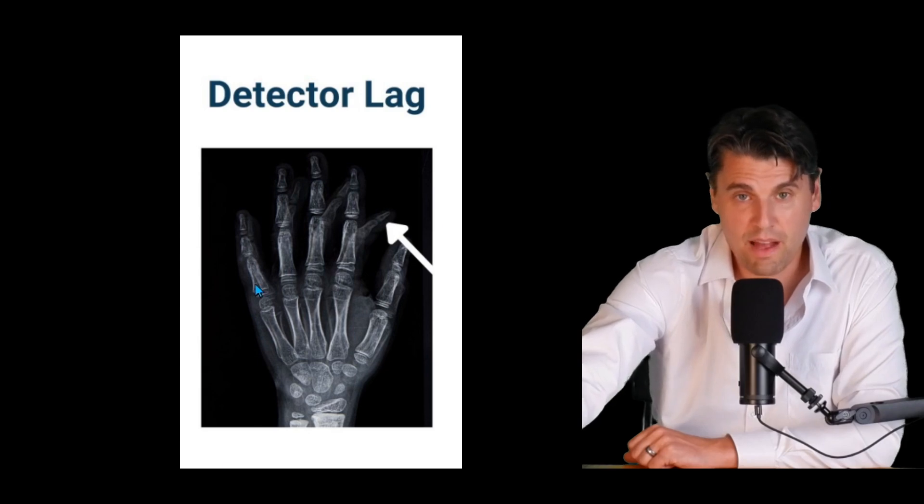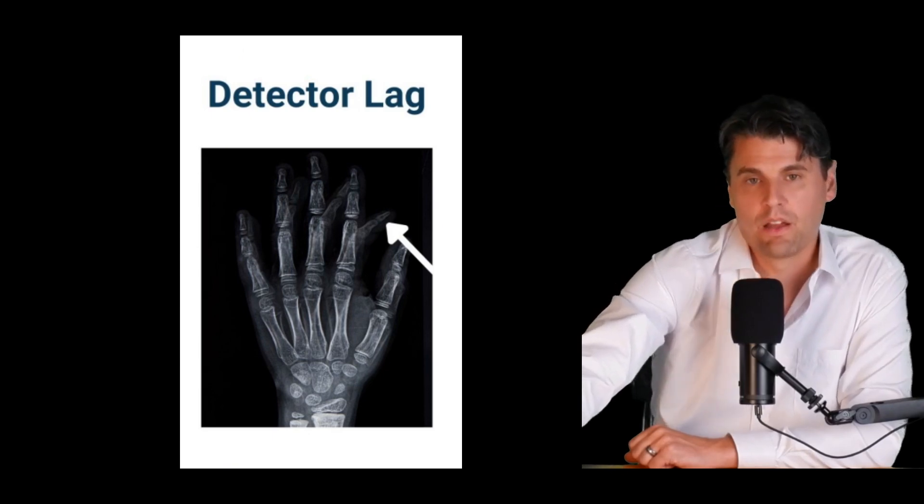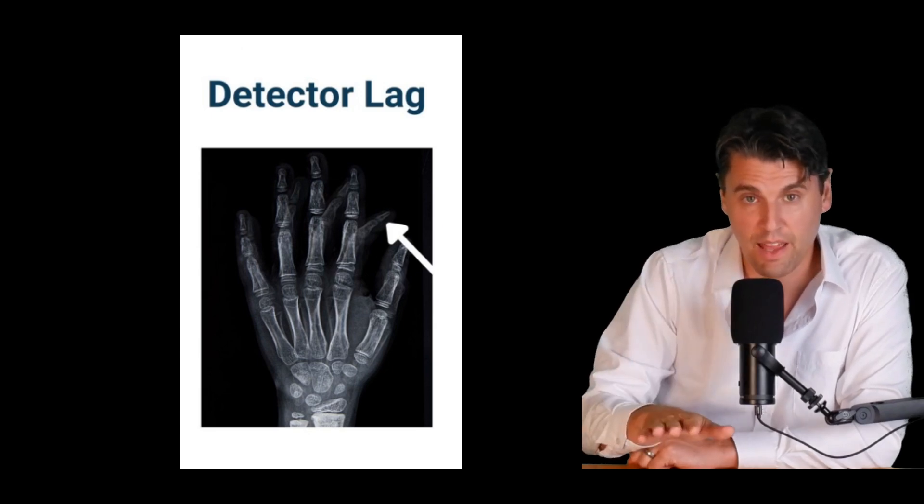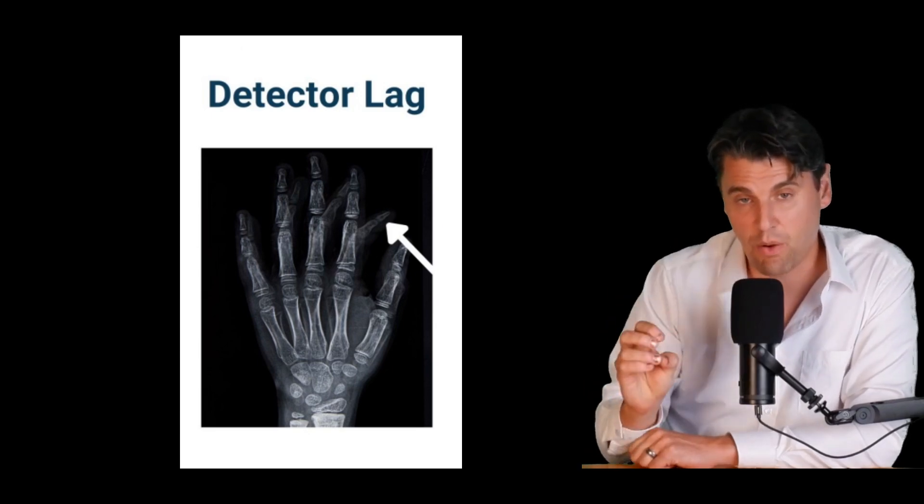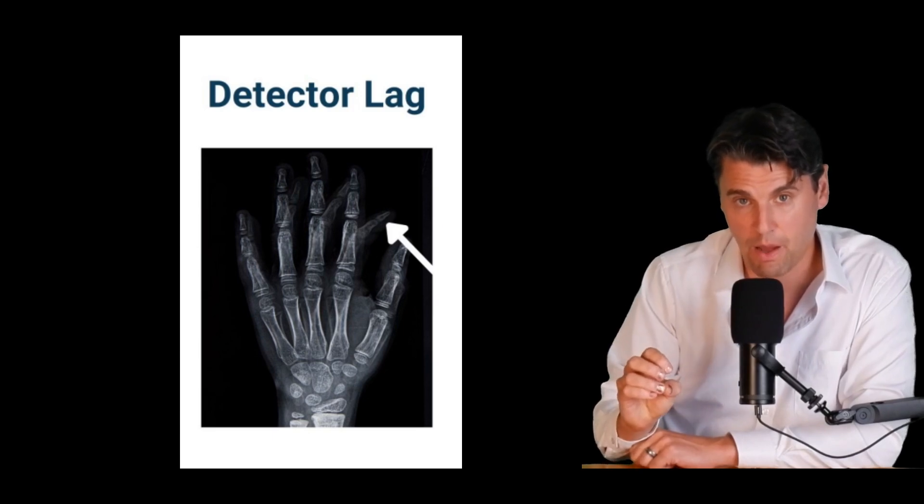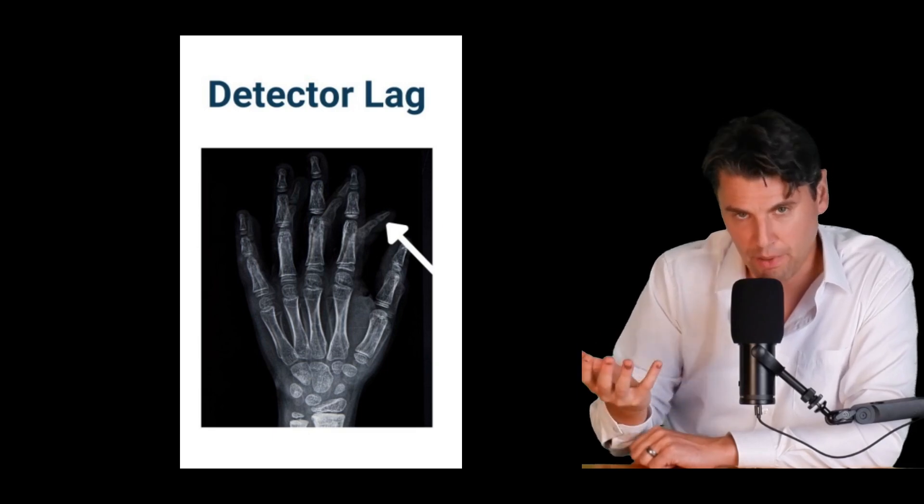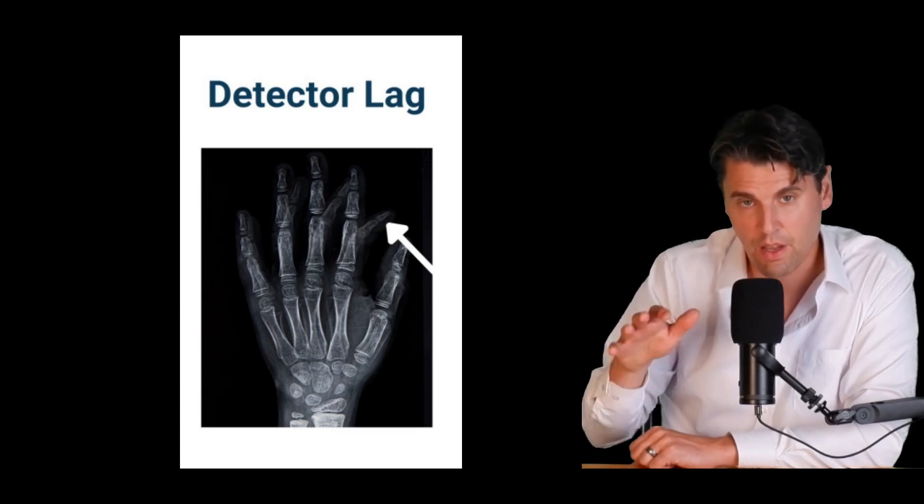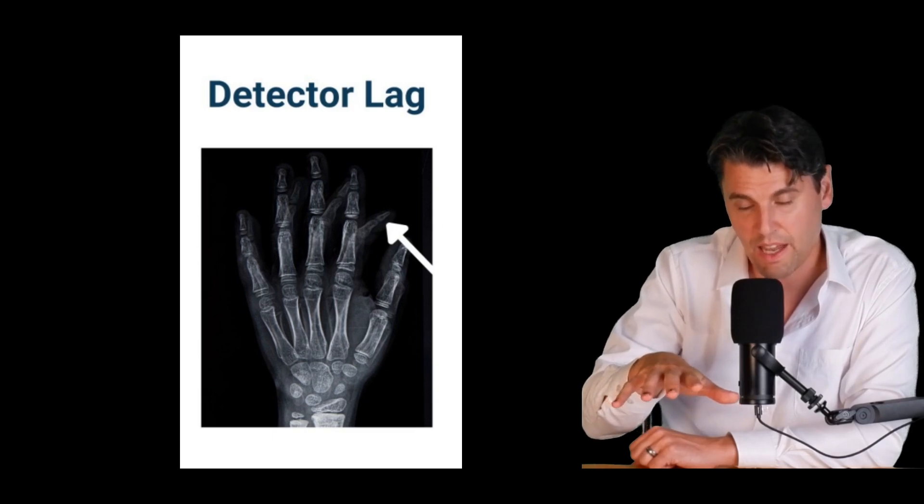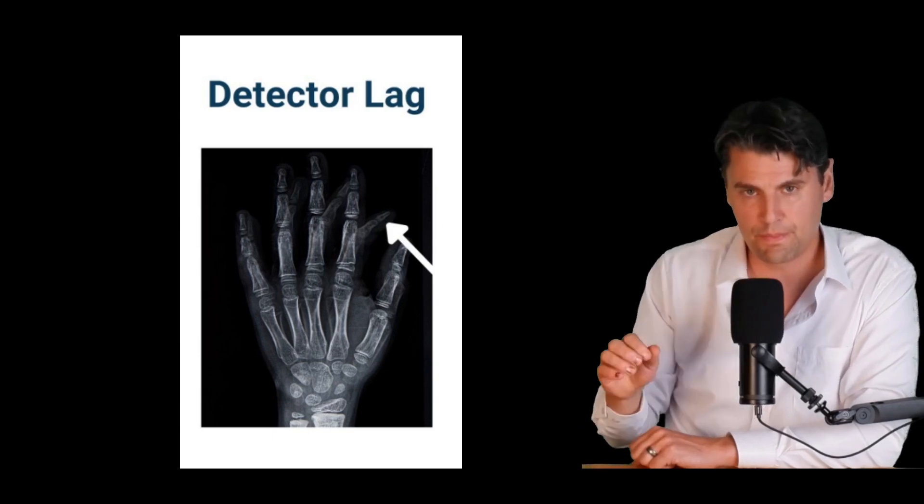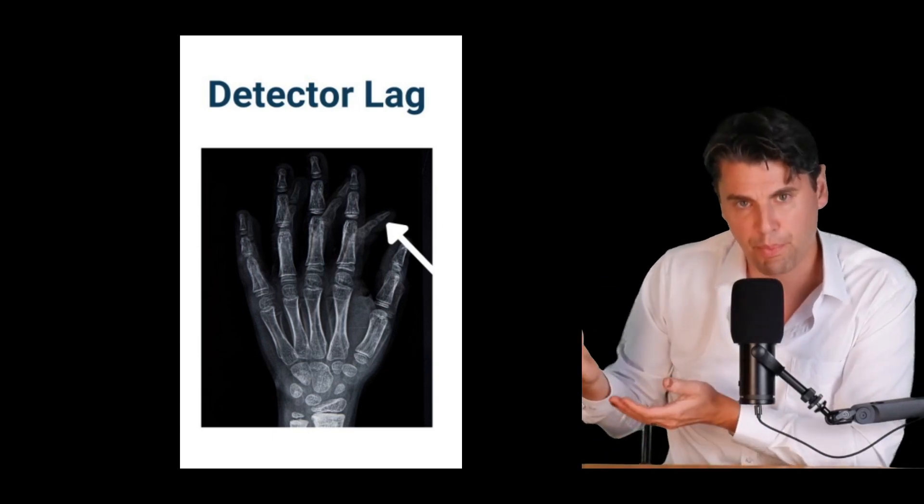There's also the possibility to have what we call ghosting in the image or detector lag where if you take an image acquisition and then you later take another acquisition this is now on a DR system that we're talking about. It has a similar visual effect to like the double exposure on the CR system where you took an acquisition and then there was motion and then you take another acquisition.